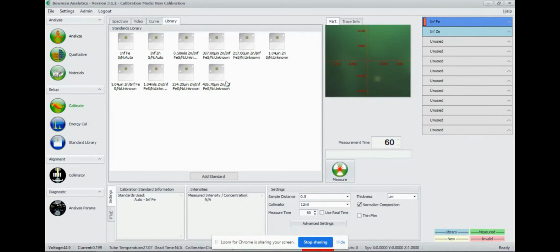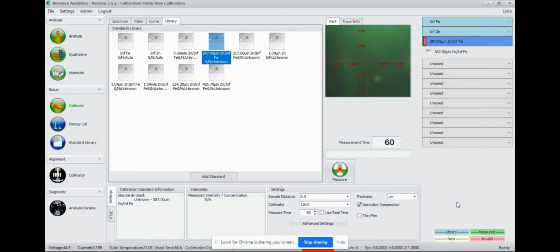Now, just because we have all of these standards doesn't mean that we're actually going to use all of them in our calibration. Steel and zinc here are already in blue. If you look down here, the library is blue, and that means it's already been measured, it's in the library, and we're just pulling that spectrum forward. If all of the standards that you want to use are already in your library, all you have to do is drag them over. So for instance, I want to use this 387 micro-inch zinc on steel standard. I'm just going to bring this over, and because it was in the library, it's blue. I don't have to do anything.